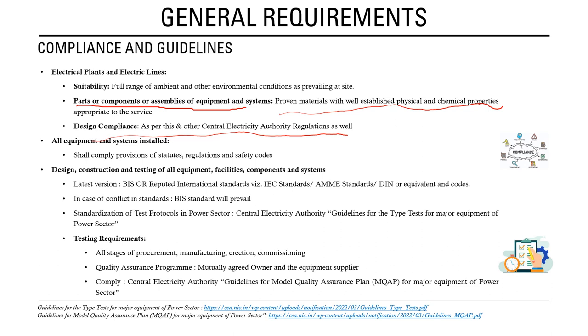For design, construction, and testing of all equipment, compliance with the latest version of BIS — Bureau of Indian Standards — or any reputed international standards like IEC, DIN, or their equivalents is required. In case of conflict between Indian and international standards, the Indian standard will prevail. All testing required should be done as per protocols defined in the CEA guidelines for type testing of major equipment of the power sector.